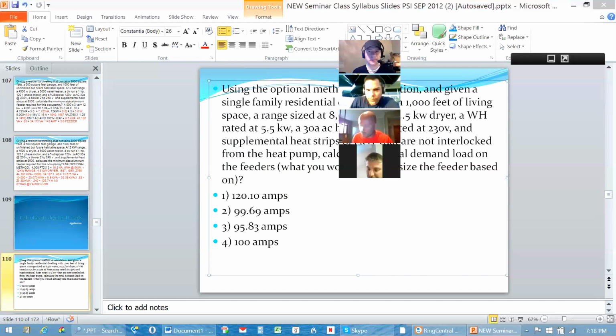On that heat strip, you went 65%, right? Yeah, only because I gave you that it wasn't interlocked, so it's going to operate at the same time as the heat pump would work. So we'd have 5.5. 5.525. Yeah, it's added to the 6,900 for the heat pump. So again, that's just 65% of that 8,500 for the heat strips.